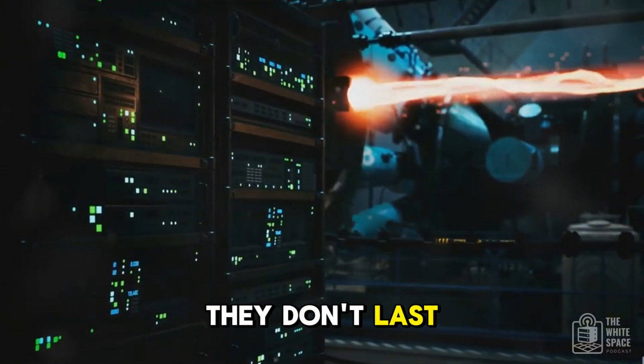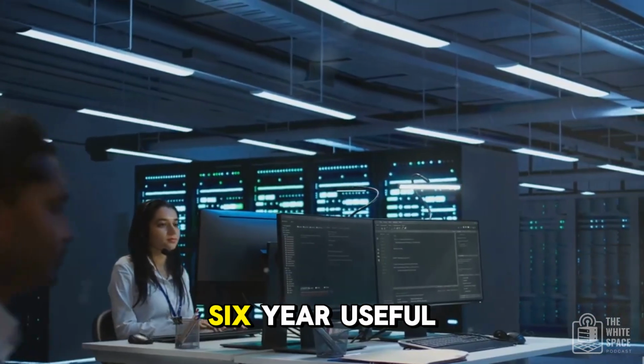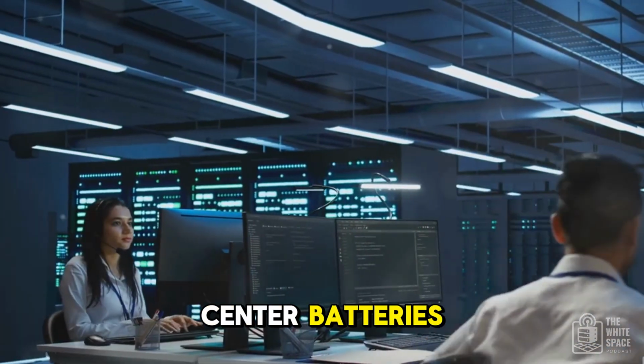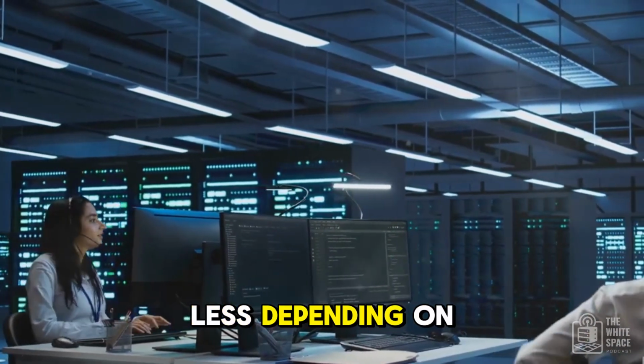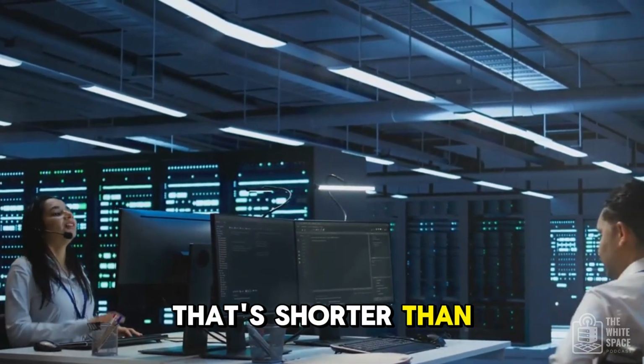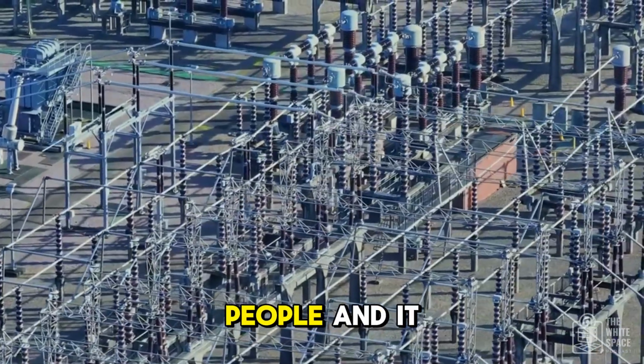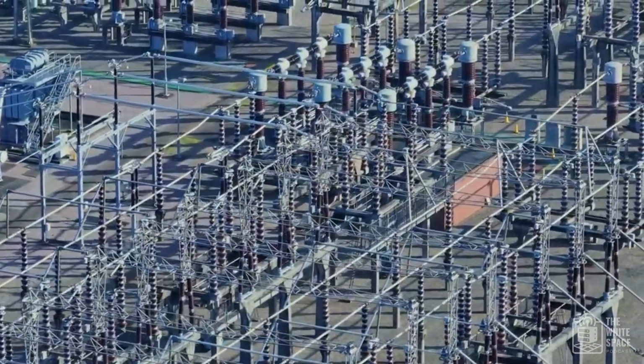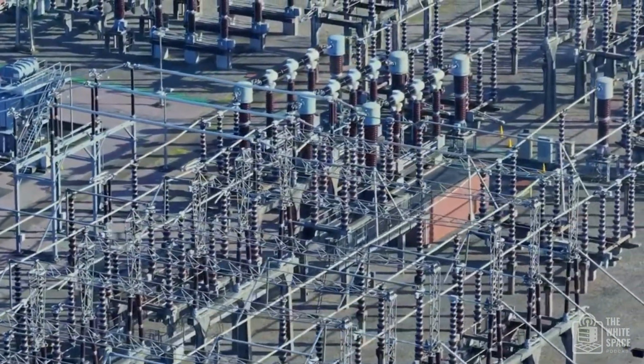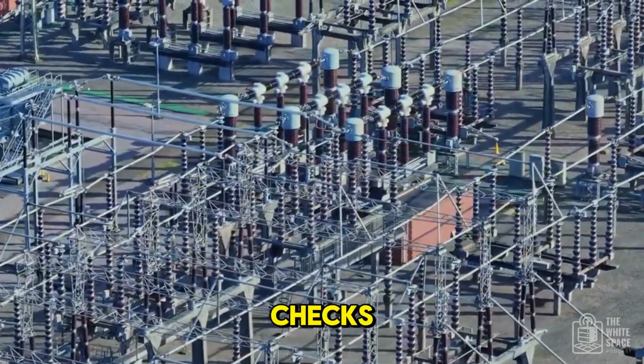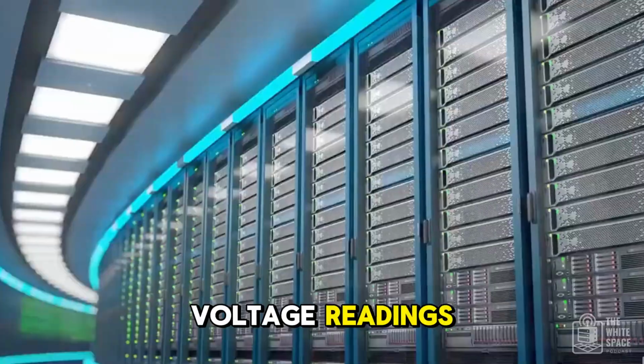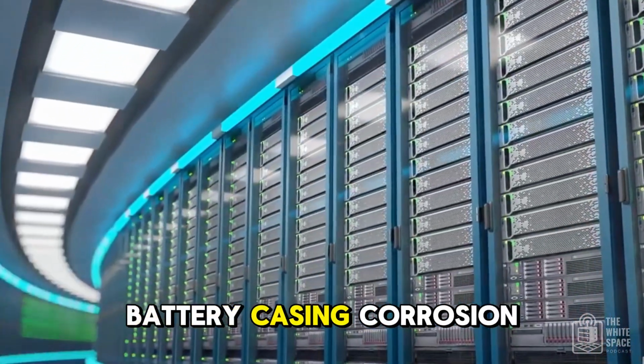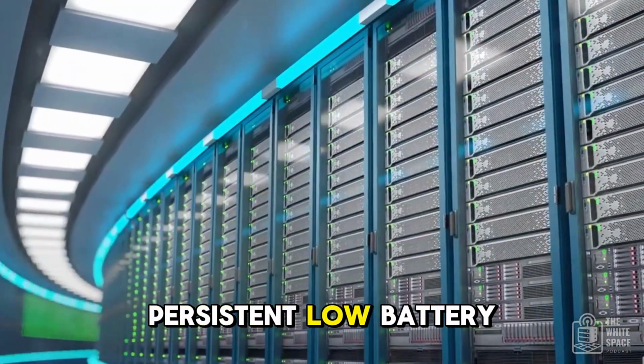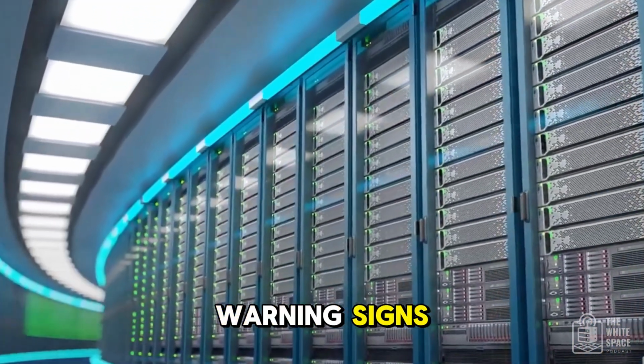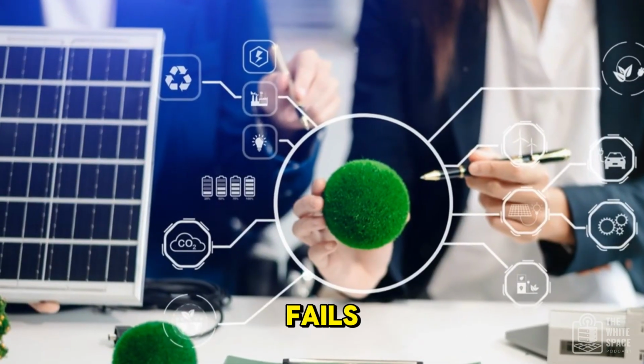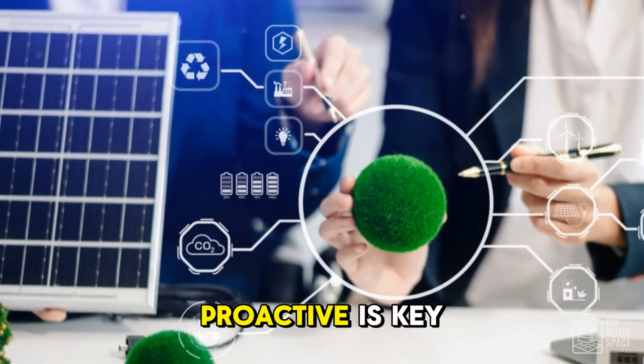It is. And they don't last forever. Typically, you're looking at a 5 to 6 year useful life for standard data center batteries like VRLA, sometimes less depending on conditions. 5 to 6 years. That's shorter than a lot of other gear. It often surprises people, and it means you have to stay on top of maintenance, semi-annual inspections, testing. That's crucial. What are you looking for in those checks? Things like low voltage readings, any signs of swelling on the battery casing, corrosion, persistent low battery alarms from the UPS. These are all warning signs. You want to catch a failing battery before it fails during an actual outage. Makes sense. Proactive is key.